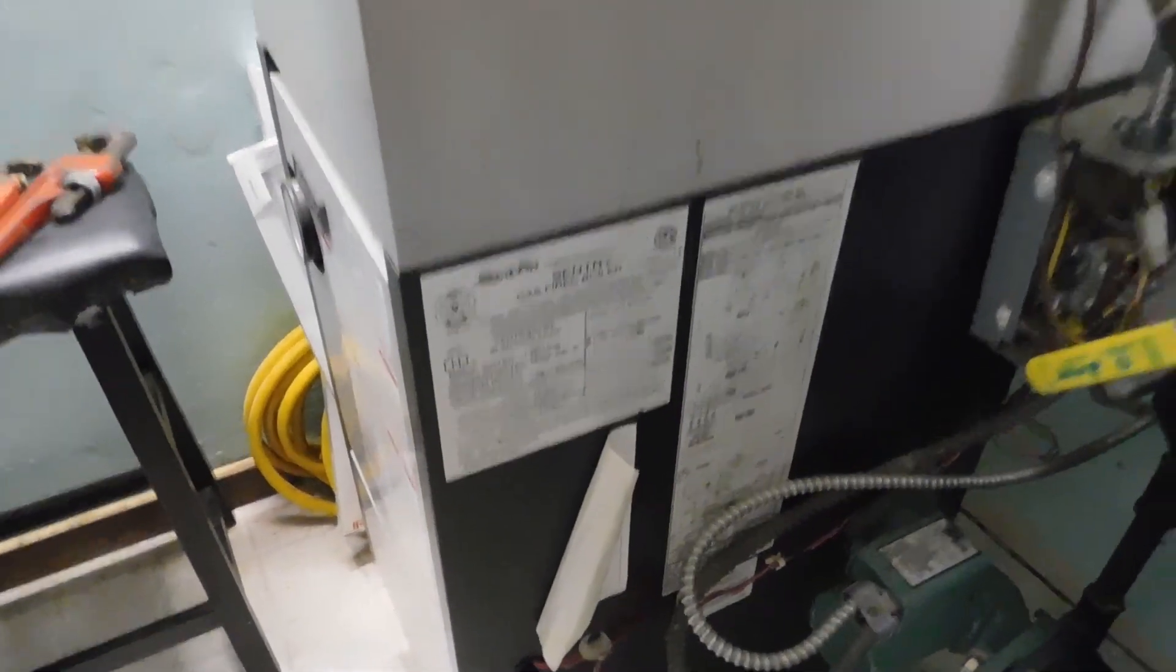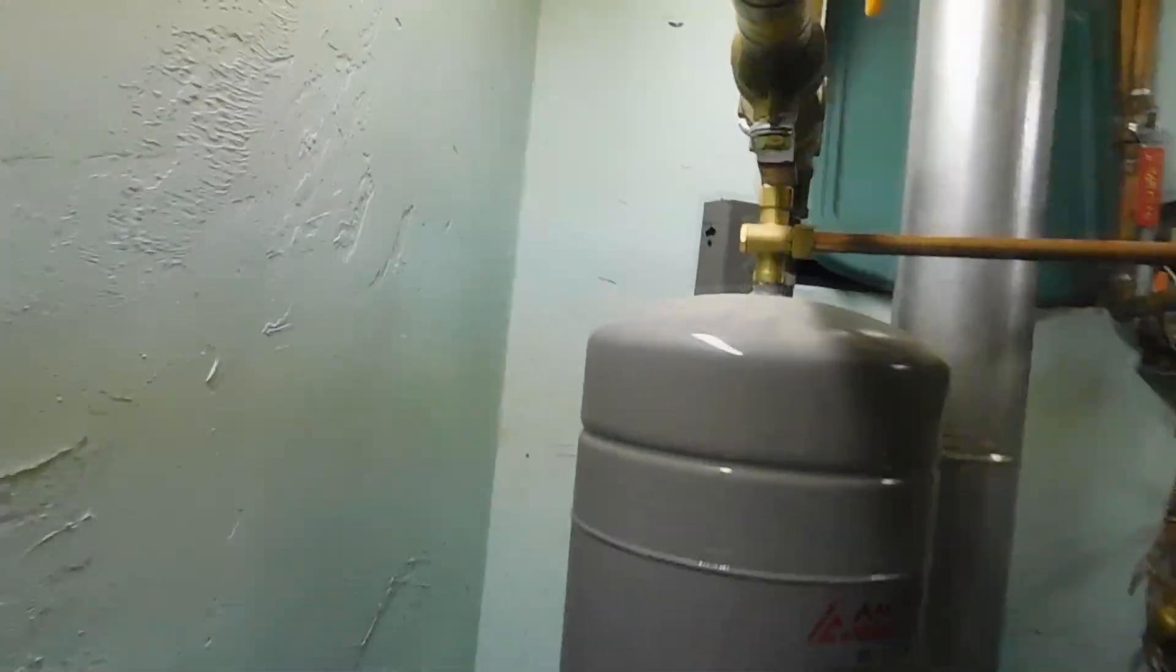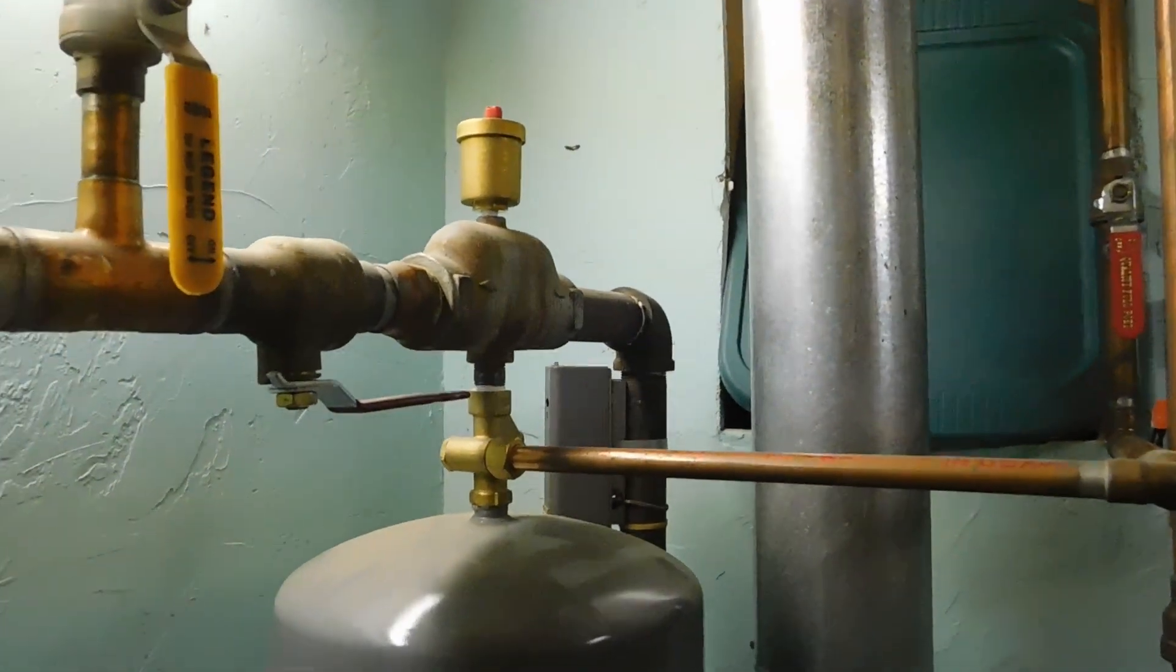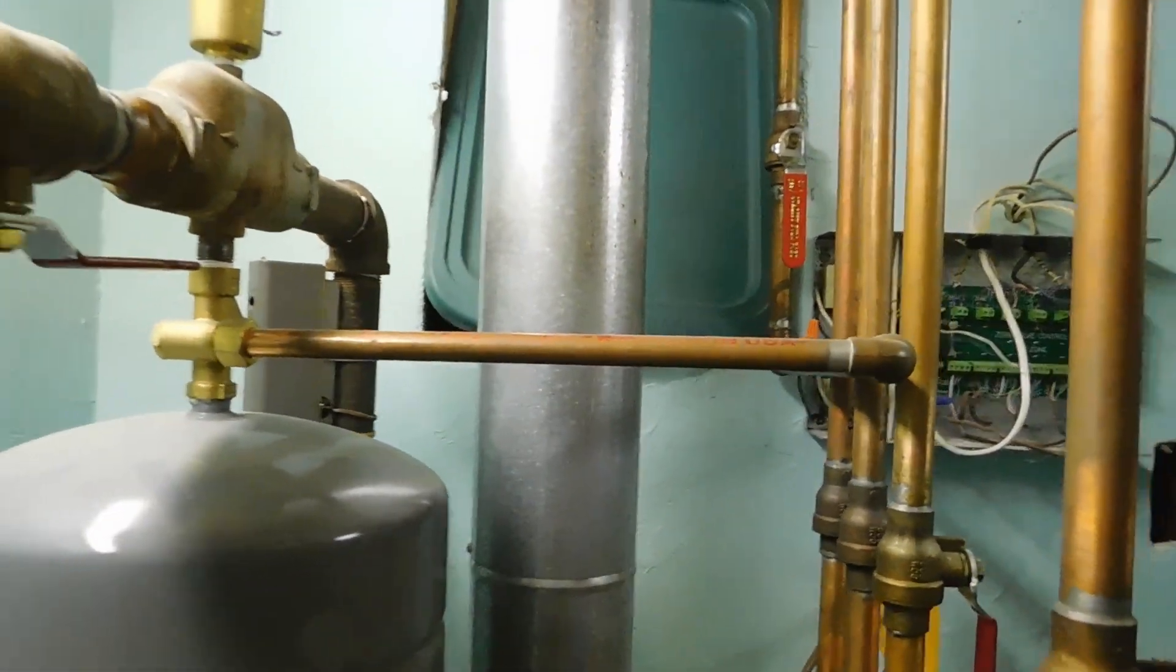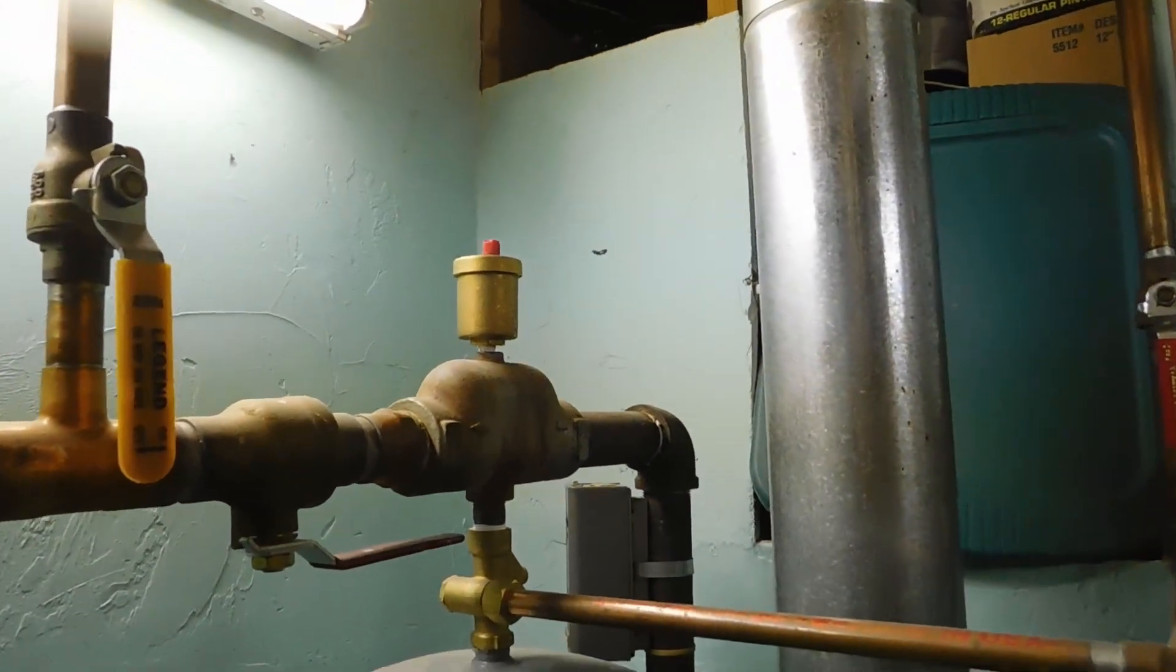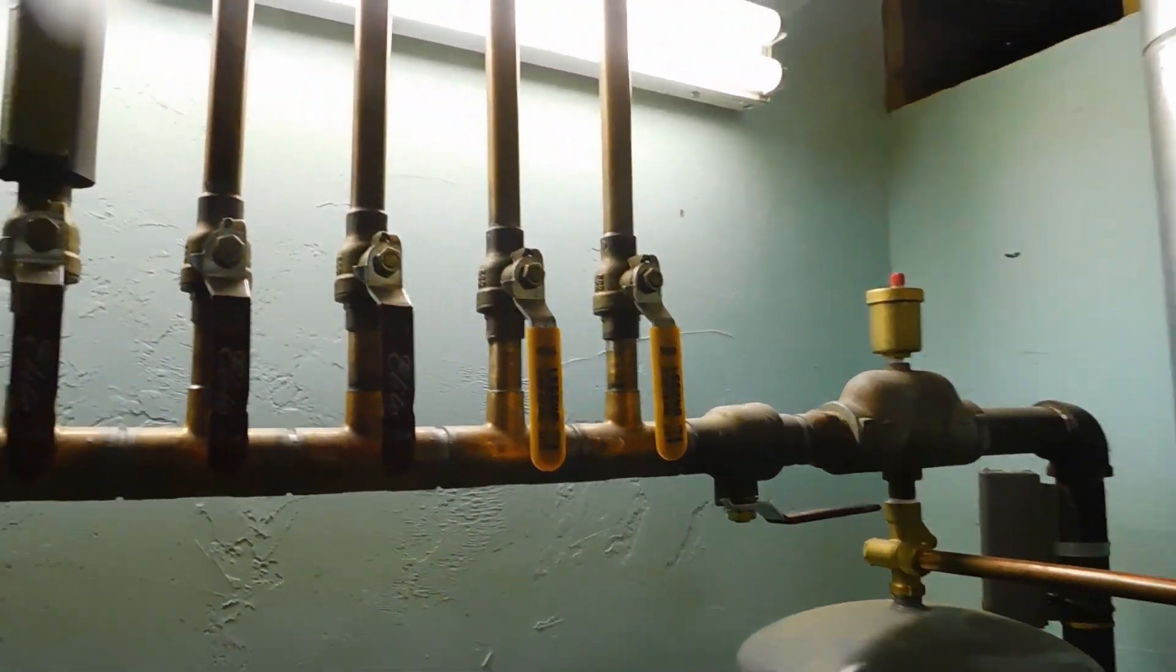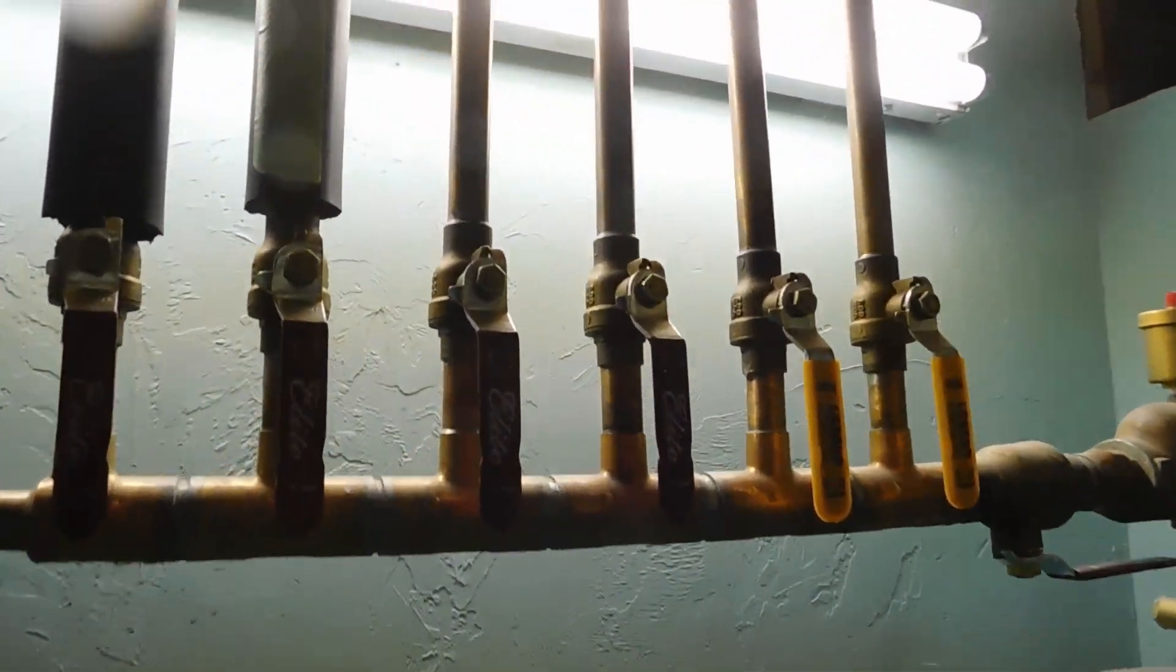Gets pumped out up and around. Supply manifold has a pressure tank, it has a feed line right off the domestic side with a check valve, the aerator or vent, and then into the supply to each of the zones.